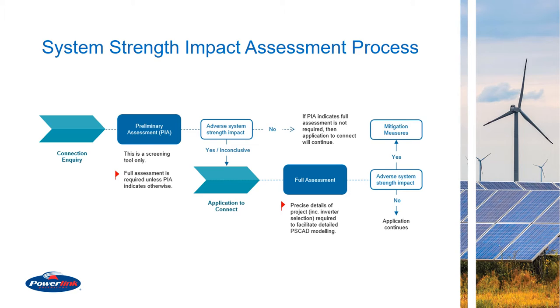And as part of the full impact assessment, NSP must identify whether this new generator is causing any adverse system strength impact or not. If adverse system strength impact is identified due to this new application, then it's the generator's obligation to propose mitigation, and NSP will assess whether that mitigation is sufficient to remediate the adverse impact or not, and that mitigation measure then becomes part of the application and the generator performance standard.